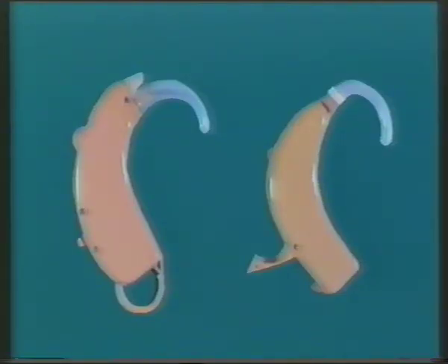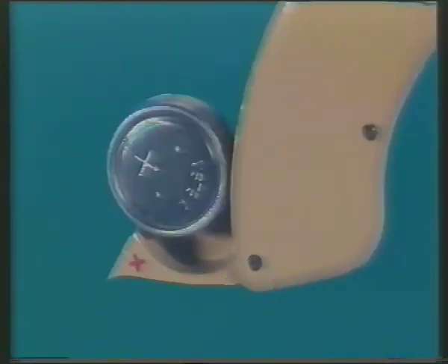The battery drawer may be at the back or base of the hearing aid. It may open in either direction. When you open it, you'll find a small cross on one side of the drawer. Usually, the bottom of the drawer is slightly convex. The battery must be inserted the correct way round.